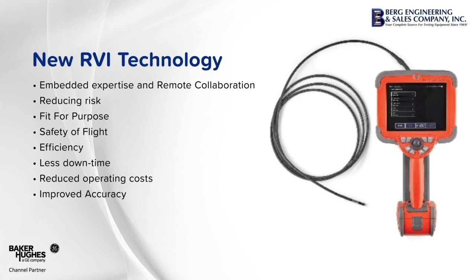But while these video borescopes are of critical importance for visual inspections in these applications, the potential of what previous RVI tools could yield remains somewhat limited by resolution, or the ability to resolve an indication in an inspection area. On the spot decision making is subsequently hampered by the standard definition provided and the limited working range that standard borescopes offer, especially when trying to determine the size of an indication. And as compliance regulations have tightened across industries, increasing pressure for more precise inspections continues to mount. At the same time, the organization must also grapple with the challenges of reducing operating costs while simultaneously making process and test improvements.